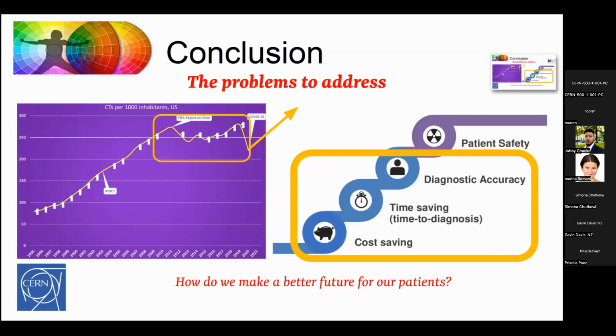That actually improves the mathematics of the reconstruction as well. One of the problems with a traditional CT is you've got a trajectory where you're spiraling around the patient. If you're firing them off almost in a random way, you get rid of a lot of the artifacts that come from the fact that you're spiraling.